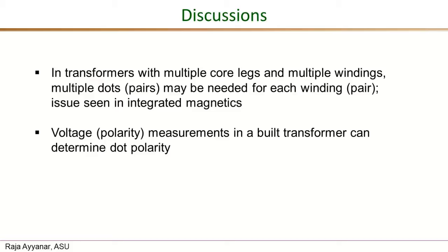The second point is that if you have a wound transformer where it is not possible to determine the winding directions of every coil, it is still easy to determine the dot polarity. All you have to do is apply a small AC voltage to any one of the windings and look at the voltage waveforms of all the other windings with respect to the applied voltage. By looking at the phase relationship, you can easily determine the dot polarity using the rules learned in this video.